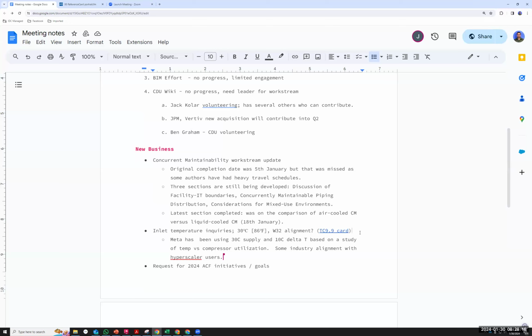Brian, I'll add that while I think we try to avoid getting a very high delta T across the chiller for the times when the chiller is being used, if you do cascade and get a very high delta T, it does present the opportunity of doing something like an inline dry cooler, doing some pre-cooling before it goes to the compressor to reduce that a little bit.